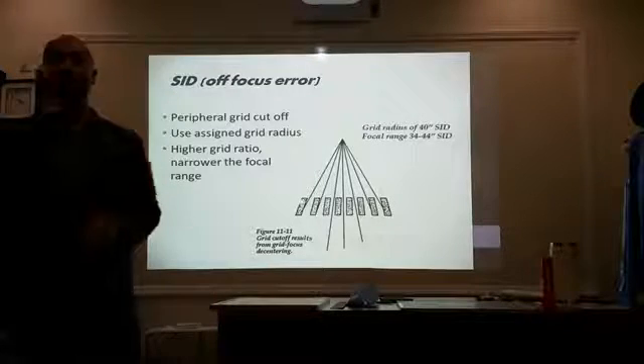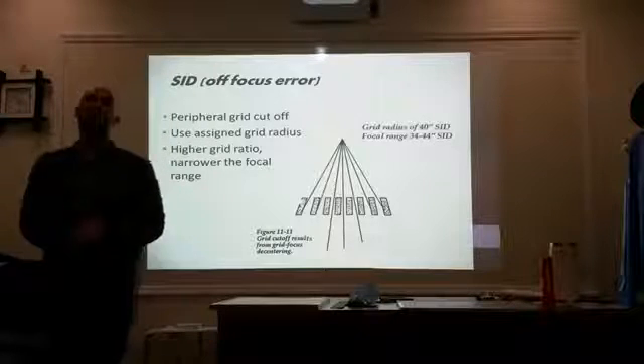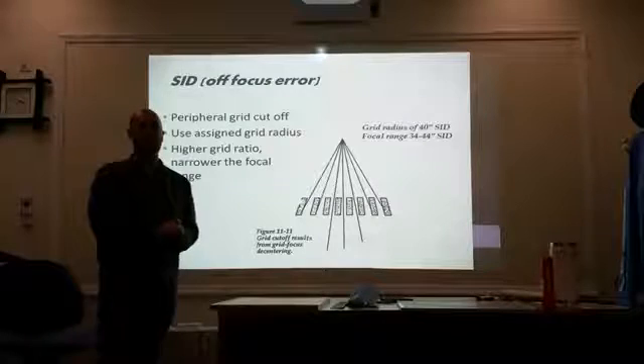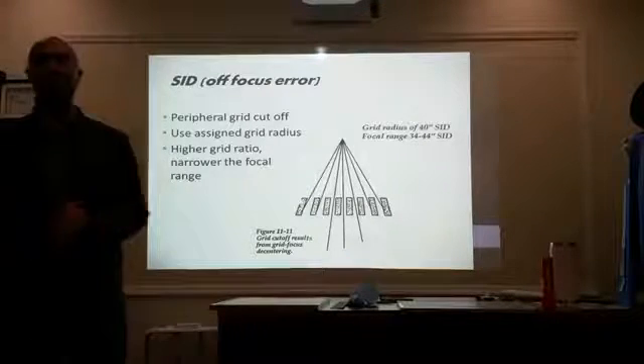Although they are going to be the most efficient and give you the highest contrast, the downside is that you have to be nearly perfect. Your margin of error becomes more narrow as your grid ratio increases.